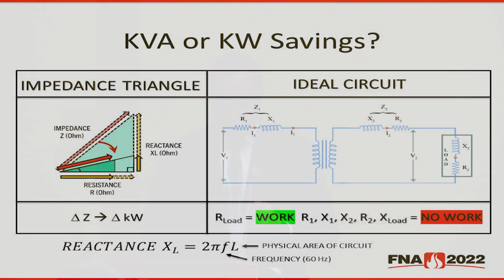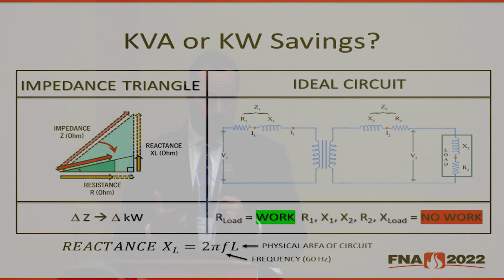The important note here is that the only component of power that's doing work is resistance in the load. The rest of the components of power do no useful work in a system, and every effort should be made to reduce them. I mentioned in the last slide that reduction in reactance is accomplished through direct current. So the equation here shows that reactance, X sub L, is equal to 2 pi FL. So this shows that reactance is proportional to the frequency of the waveform as well as the physical area of the circuit. With direct current, there is no frequency, and the reactance is completely eliminated.